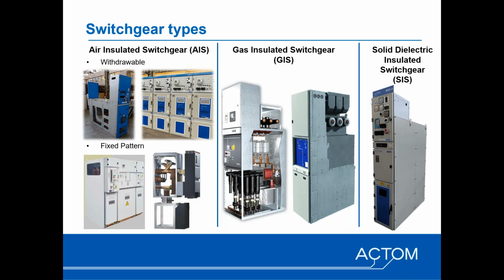Then in the middle, we've got GIS or gas-insulated switchgear. Examples there would be SF6 with sealed for life gas-filled compartments, sealed pressure systems as defined in IEC with a typical 20, 30 or 40-year lifespan over which no replenishment of gas is required. And then you've got on the right, although it may not be obvious, an example of a solid dielectric switchgear assembly. And we'll clarify now what exactly that entails and what it's about. But from the outside, effectively, it looks like a metal enclosed switchgear assembly.